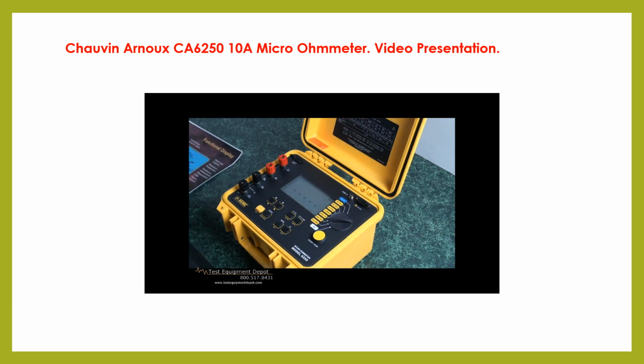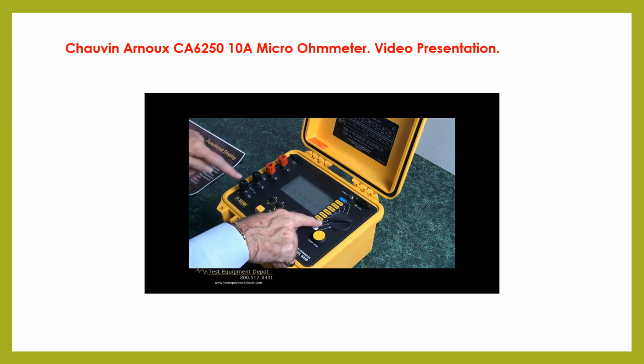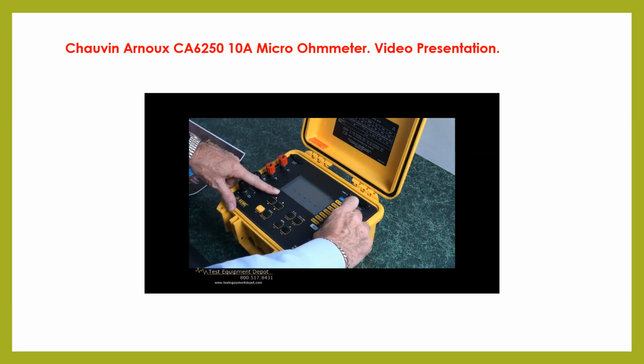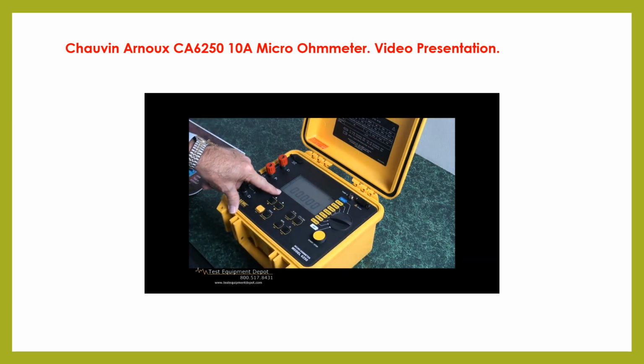We see that, for example, we have a warning buzzer. We can toggle that on and off to save the battery. If we had selected alarm, we would see that here. This will tell us what range we have selected, 250. So if I go to 100, we'll see that change to 100, and I'm on the 25 ohm scale. It tells me the test current is now 100 milliamps.